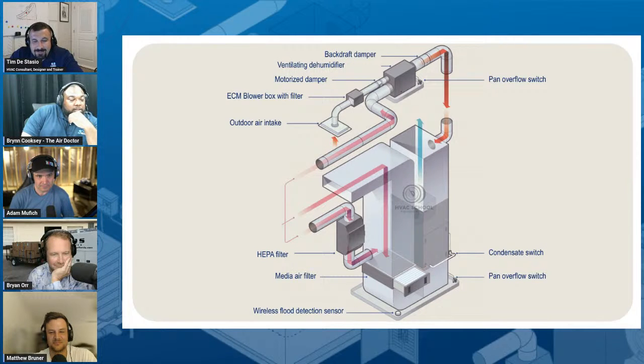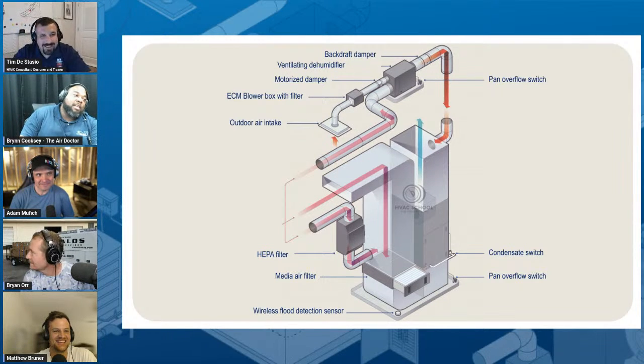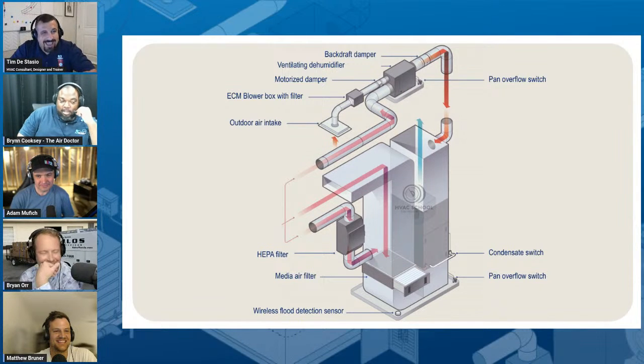You got a nice big return drop, and then of course we always see the rest of the return is always undersized with basement systems. I never got that skinny jeans return drop. A lot of times they bring in a really big return, like the horizontal is really big, and they put this tiny little return drop. I'm like, why did you do that? Crack heat exchangers all day long.